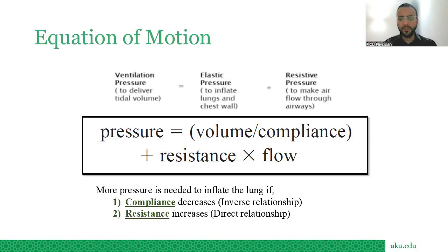Okay. One more thing: if the elastic pressure increases or the resistive pressure increases, then the ventilator will have to work extra to generate the same tidal volume. Now, down here you can see there's an equation: pressure is equal to volume divided by compliance plus resistance into flow.